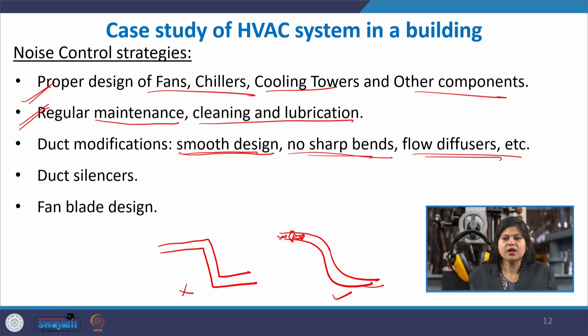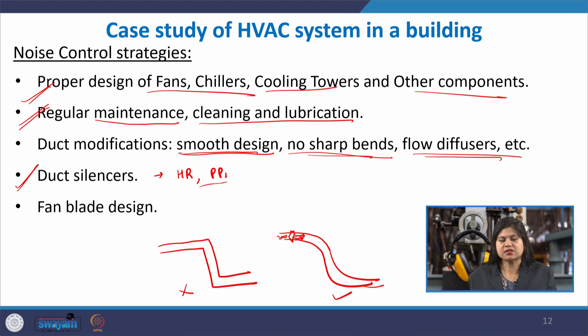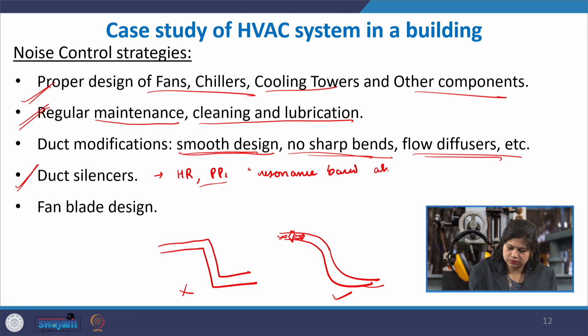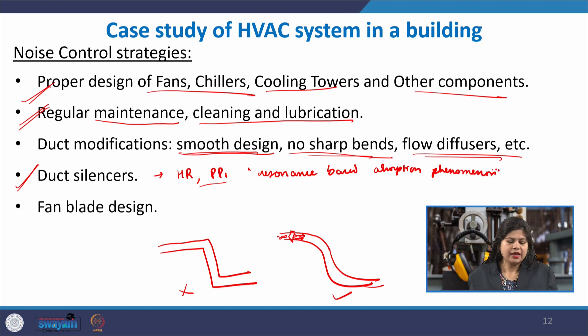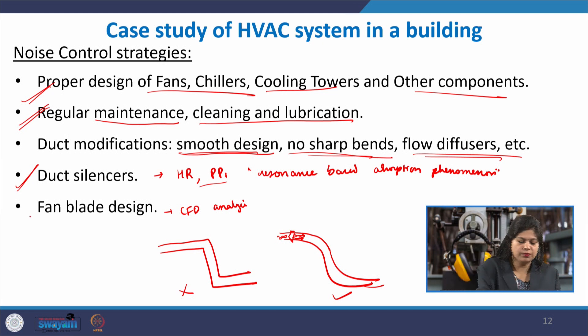Just as automotive systems have silencers in the exhaust pipe, silencers can be installed in ducts — these duct silencers typically involve Helmholtz resonators, perforated panels, and various resonance-based absorption phenomena. Additionally, CFD analysis can be used to design fan blades that produce less turbulence and smoother air flow, reducing fan noise when installed in the system.